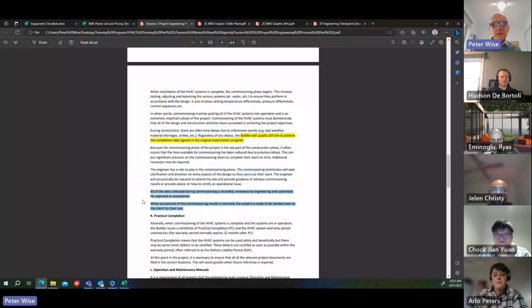If it turns out that the fan static calculations are not correct, or something's been overlooked, then maybe we need to change the fan, or find a way to increase the performance of the fan. Maybe we can speed it up, or change the pitch angle of the blades, and so on. All those sort of things you'll talk about and decide on the best way forward.